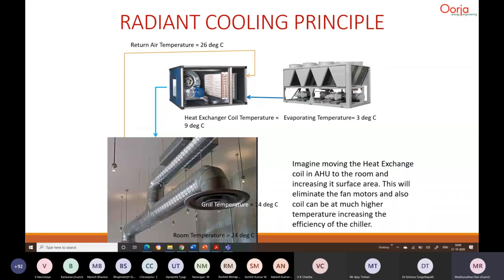We have the same box with a fan, with a coil connected to a network of ducts. Nothing has changed in that except those motors are now connected to VFD. So it is this part that we want to bring efficiency in. If we bring efficiency in the distribution part, that will cascade upwards and provide efficiency even in the generation side without doing anything, even if you use any kind of chiller. How is that? I'll explain.